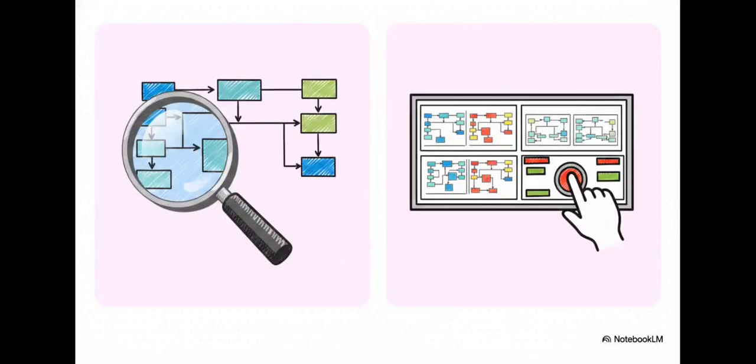Now, this really illustrates the contrast when we start moving into advanced dashboards. Think of the Pcs7 SFC control as your magnifying glass. It gives you a focused, single-sequence view triggered by just clicking a button. But the multi-chart control operates on a totally different scale. It's your watchtower. You roll out the multi-chart when operators need a macro view of the entire plant, overseeing multiple sequencers simultaneously.